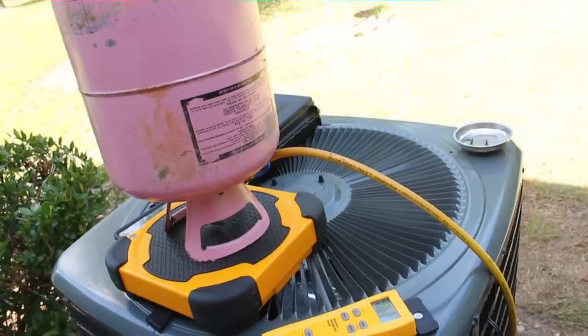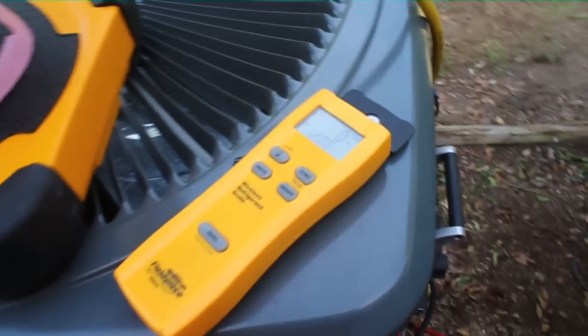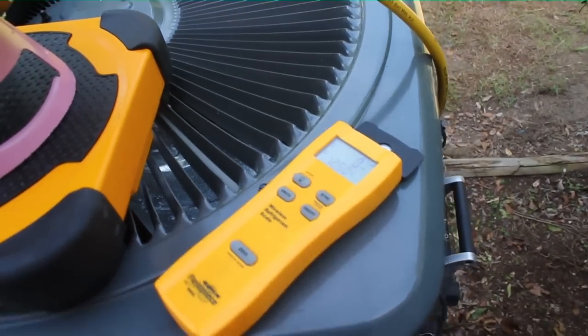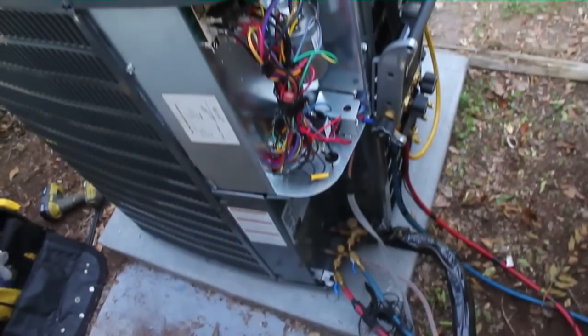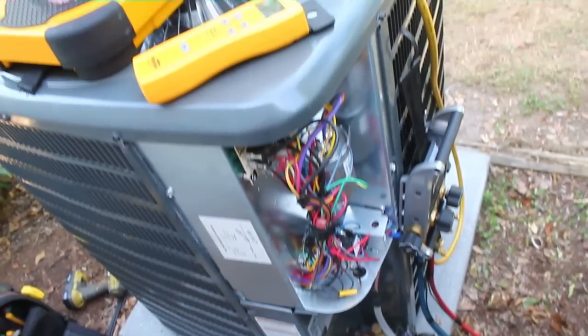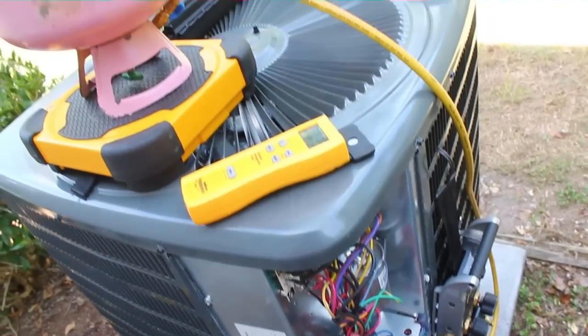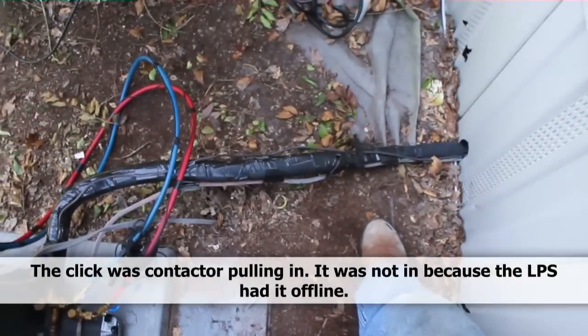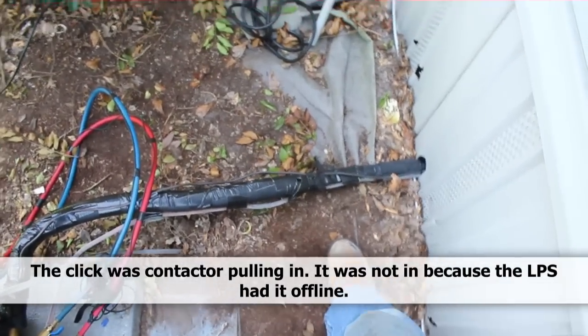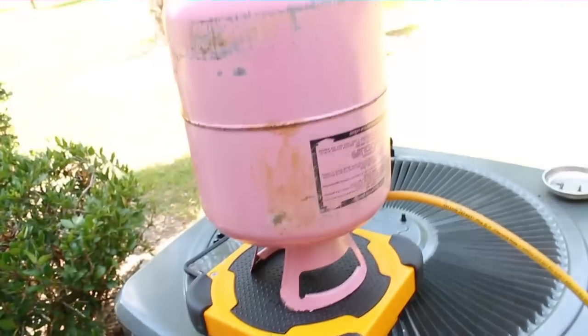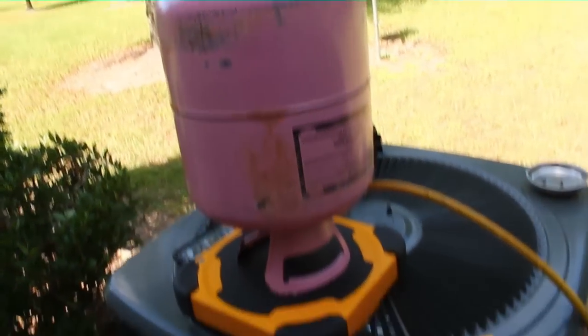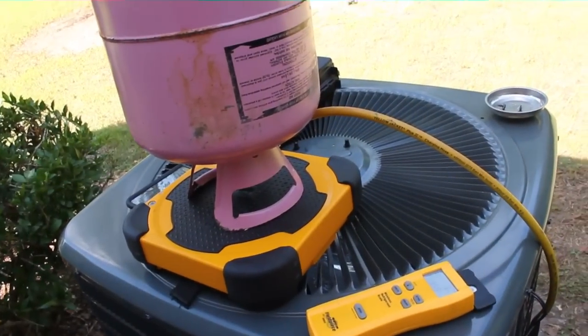Have the R410A out, putting refrigerant into the unit. As you see, we are about a pound into it. 11 pounds total, probably go to about 10. We have a very short line set. This is a single wide trailer, so the line set goes right through the wall, and boom, you hear that click. That was a low pressure switch going in. Line set goes right through the wall, right to the electric furnace and coil. So we'll start with 10 pounds and go from there.